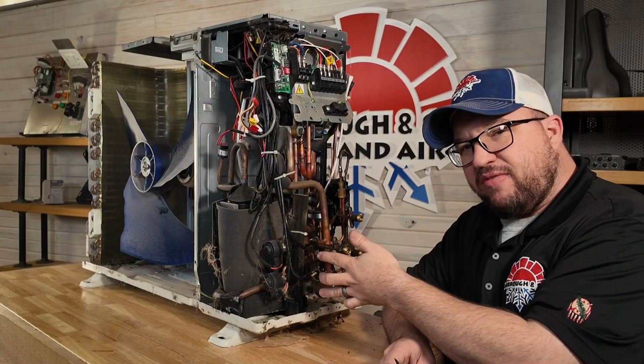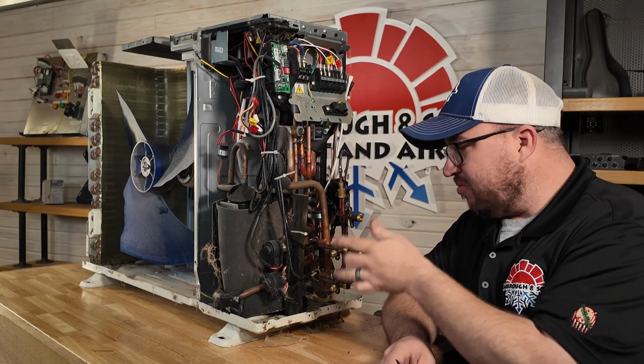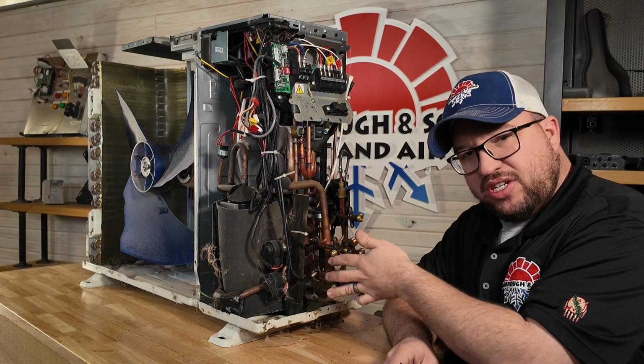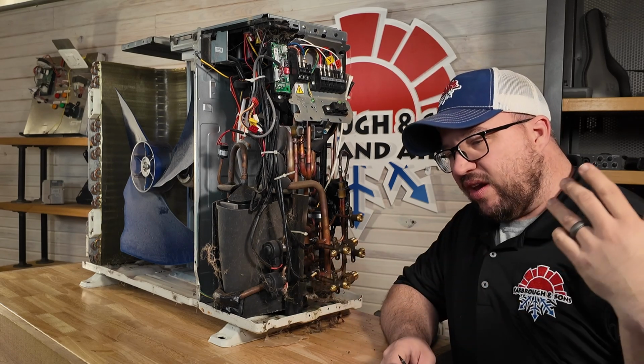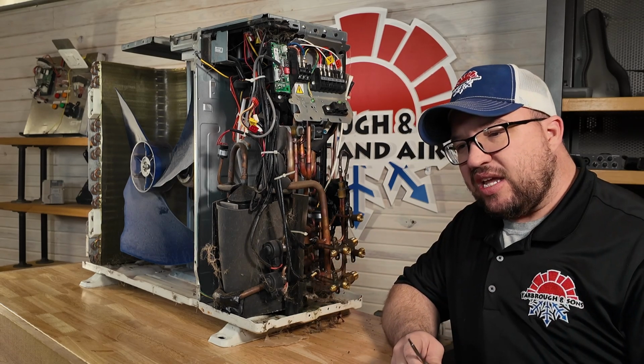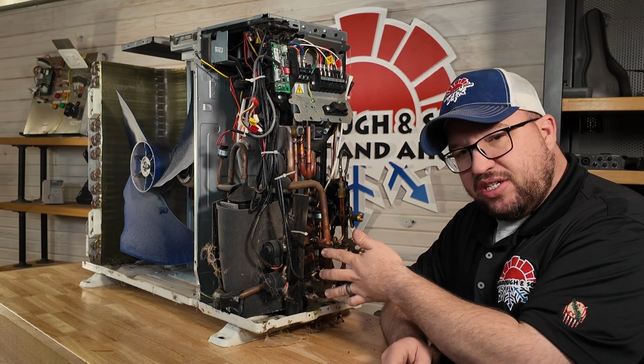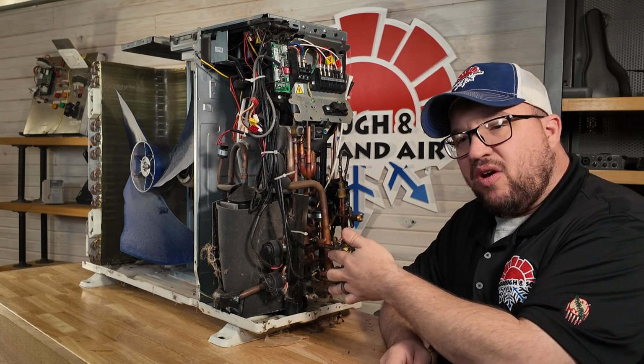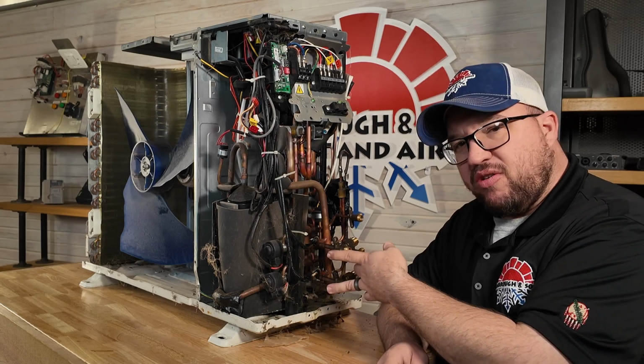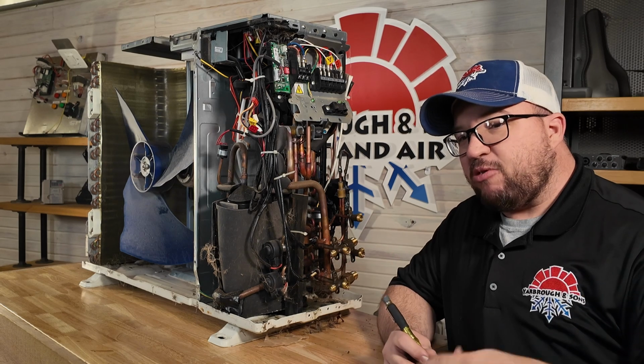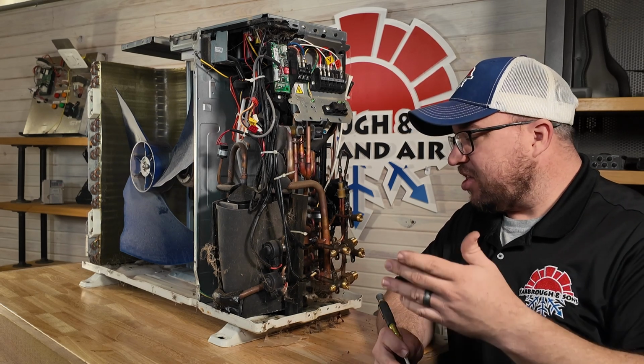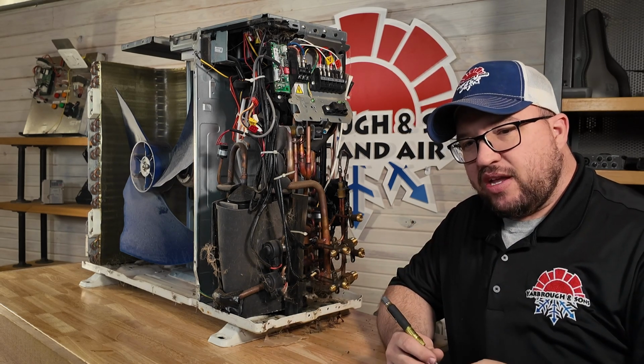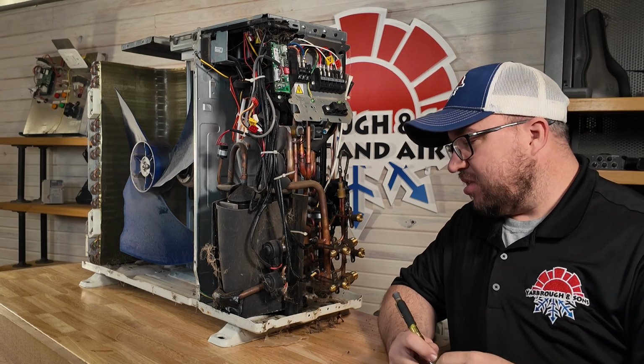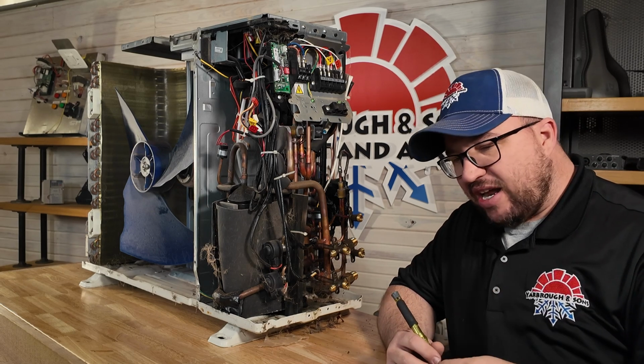Typically when you have a service valve, you usually have service valves on your, what we call, liquid side and your suction side. Now on mini splits, it does not. It will only have it on the suction side. So we can only tie our refrigerant gauges onto your actual suction. That brings up a problem with some service techs because we actually can't calculate superheat and subcooling with these units. But really not a big deal.